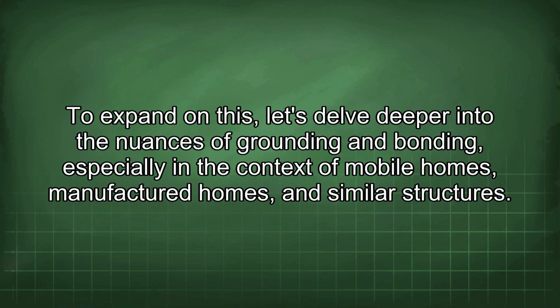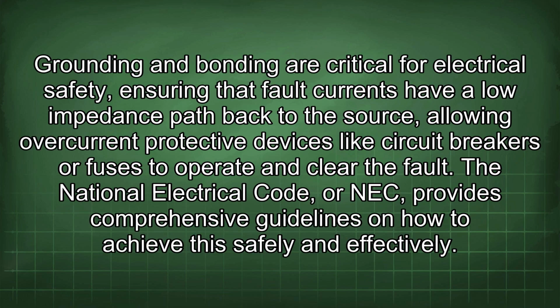To expand on this, let's delve deeper into the nuances of grounding and bonding, especially in the context of mobile homes, manufactured homes, and similar structures. Grounding and bonding are critical for electrical safety, ensuring that fault currents have a low impedance path back to the source, allowing overcurrent protective devices like circuit breakers or fuses to operate and clear the fault. The National Electrical Code, or NEC, provides comprehensive guidelines on how to achieve this safely and effectively.